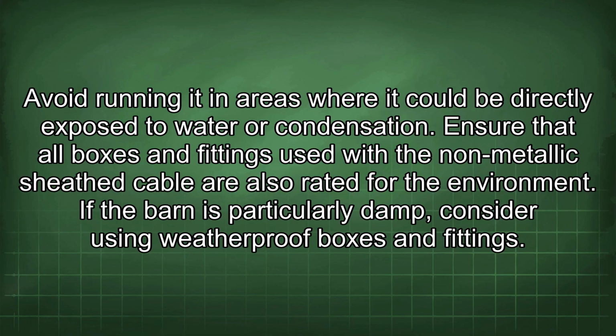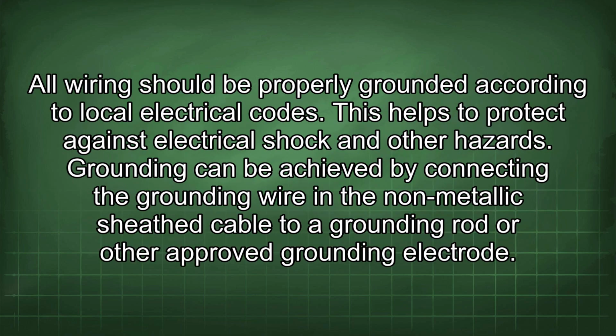Ensure that all boxes and fittings used with the non-metallic sheath cable are also rated for the environment. If the barn is particularly damp, consider using weatherproof boxes and fittings. All wiring should be properly grounded according to local electrical codes. This helps to protect against electrical shock and other hazards.